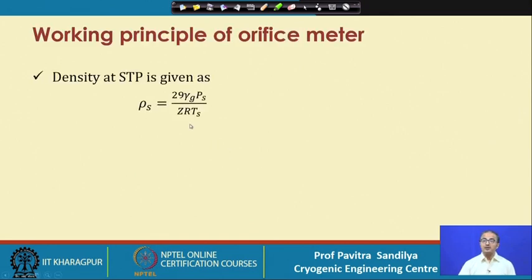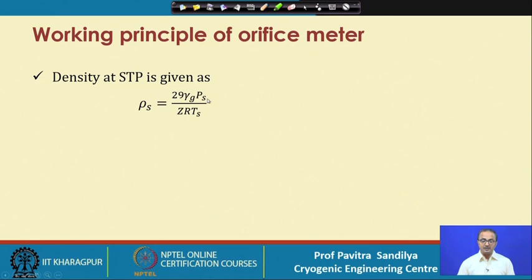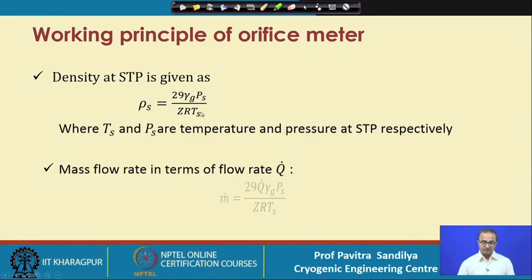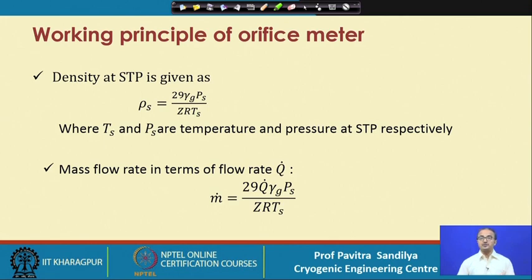In natural gas industry, we always refer to standard conditions. We define the density at standard conditions using the same gas law but substituting standard pressure and standard temperature, and then express the mass flow rate in terms of standard conditions. We must remember the mass flow rate remains the same irrespective of pressure and temperature, but the volumetric flow rate changes with pressure and temperature.